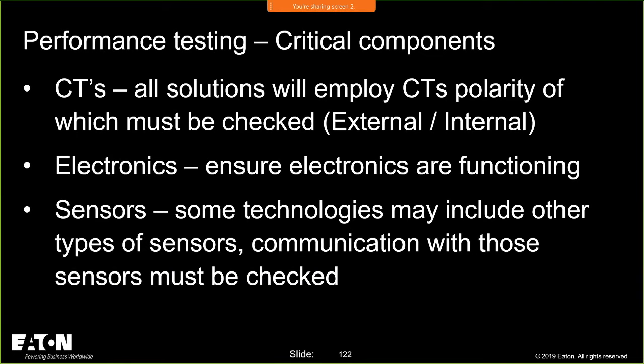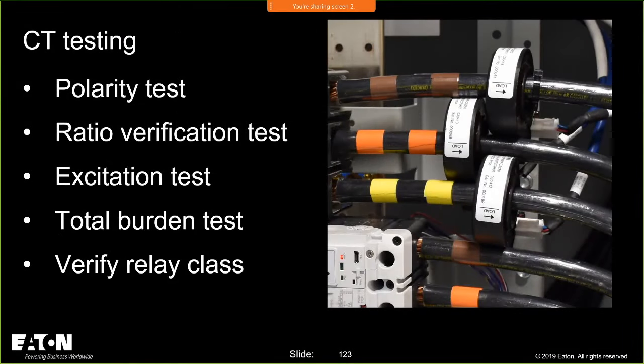When you have CTs, you have to test the CTs, the electronics, and any of the sensors. So when I have CTs in the picture, these are some of the tests we're going to be doing: polarity test, verifying the ratio. If it's a 300:5, make sure it's a 300:5. These arrows, those stickers aren't always put on the right way every time. We've seen them where they were not labeled correctly, so it's important to do it.